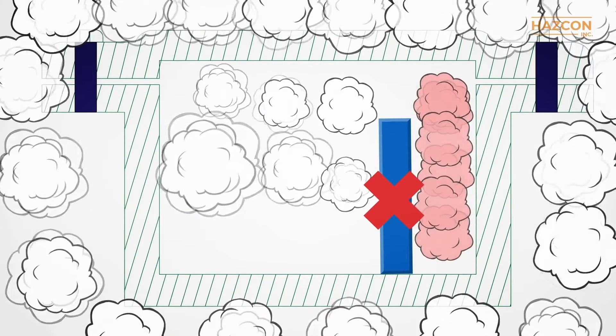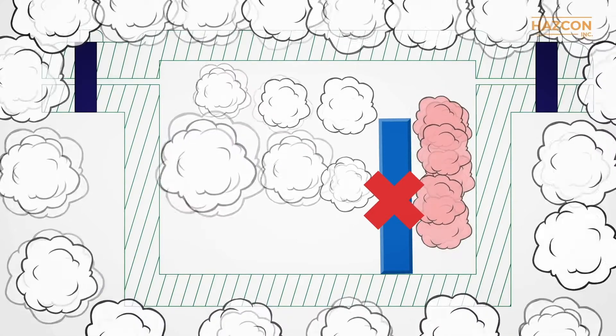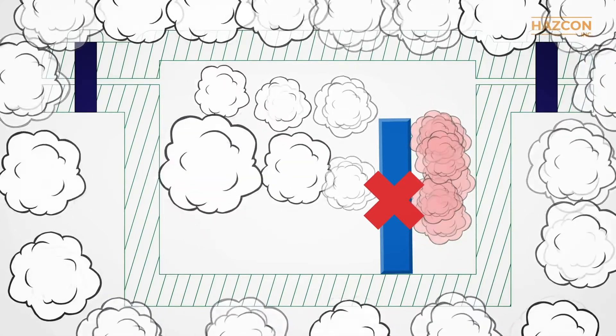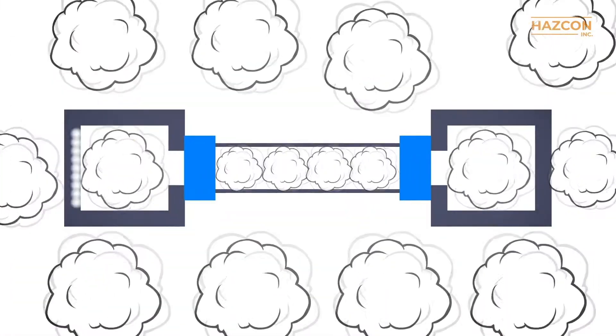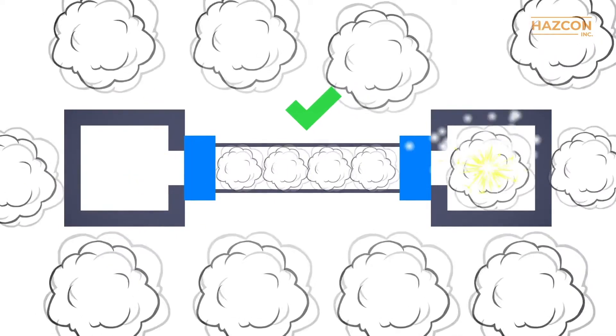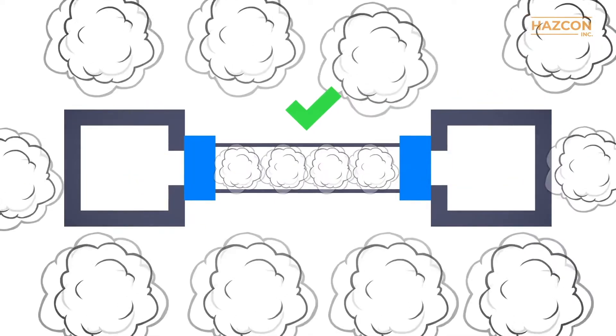Prevent unburned gas from collecting within an enclosure. This should be considered in the design of the enclosure. Use stopping plugs or sealing material to seal off one enclosure from another and to seal off the conduit system.